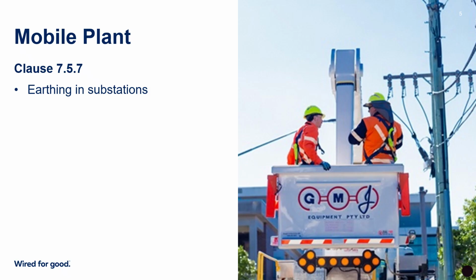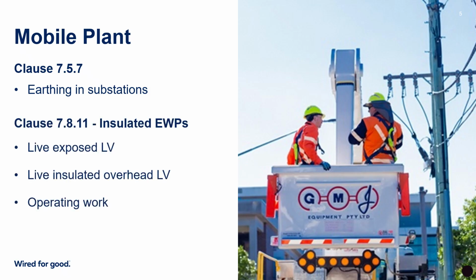There are changes to the requirements for earthing mobile plant in substations in Clause 7.5.7. A new Clause 7.8.11 sets out the tasks where, if the work is to be carried out from an elevated work platform or EWP, the EWP must be insulated. These tasks are work on or near live exposed low voltage mains and apparatus, work on live insulated overhead mains and apparatus, and operating work other than the earthing of mains and apparatus that are already earthed. Uninsulated EWPs must not be used for these tasks.